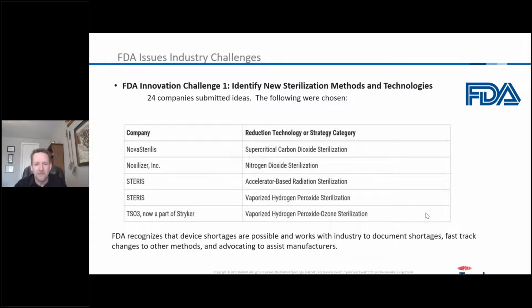So the FDA came in. The EPA is more dealing with the air pollutants and that type of thing, the environment. FDA obviously is looking at the medical device supply chain and patient safety. So they issued a challenge to the entire industry, and it was a two-part challenge. The first one said, okay, can we identify new sterilization methods and technologies? Is there anything out there that can replace ethylene oxide? So 24 different companies submitted ideas. And not every company that has a different type of sterilization submitted that. There's some out there that are good methods of sterilization that weren't submitted, but the FDA chose the following ones.